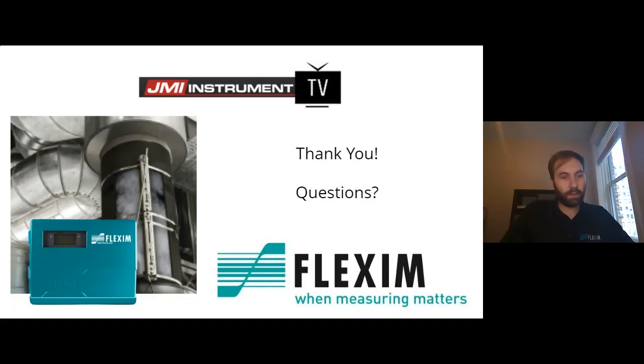Okay. The next question is, is EtherCAT communication available? I think they mean Ethernet, but I could be wrong. I think so too. We have two protocols that we use. One is a building automation protocol called BACnet, and we have that both in RS-485 and Ethernet, or MSTP and TCP/IP. And then we also use Modbus TCP/IP and Modbus RTU. All right, so that would be a big yes, and I'm typing some of the answers in the chat as well.